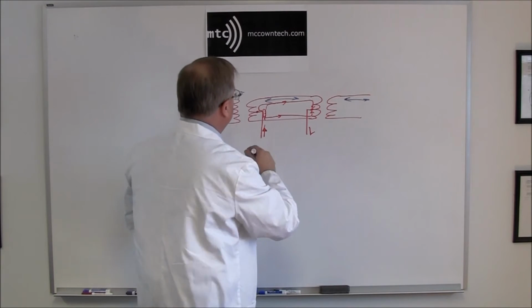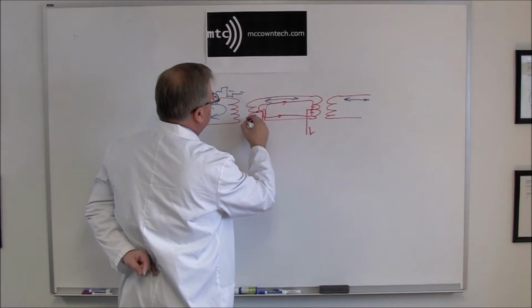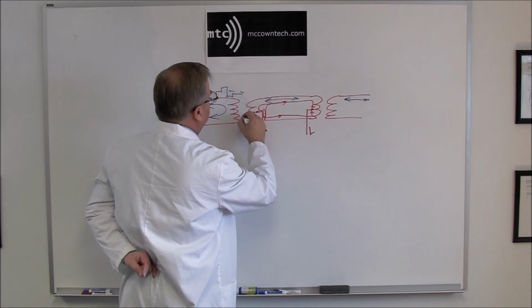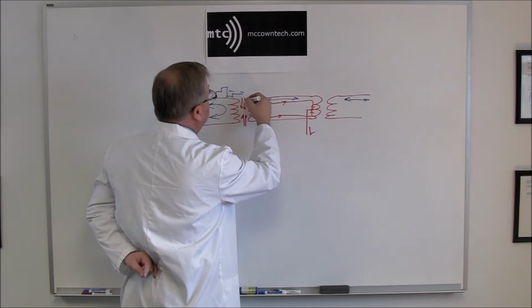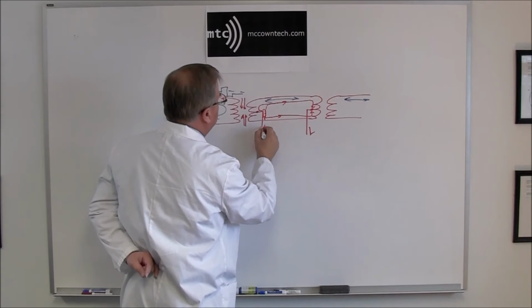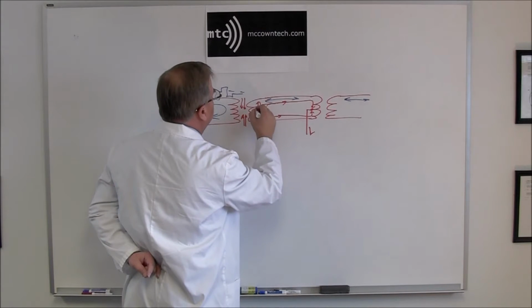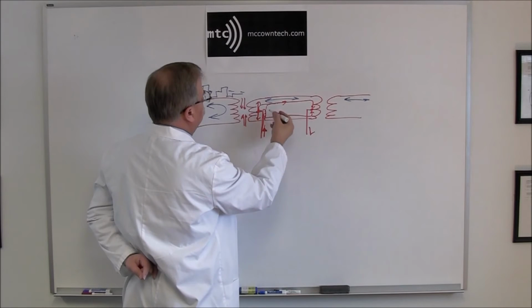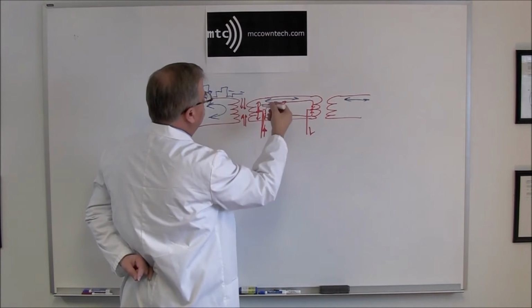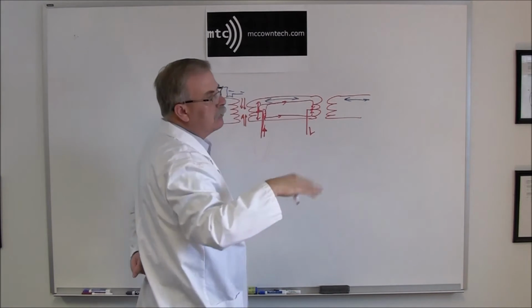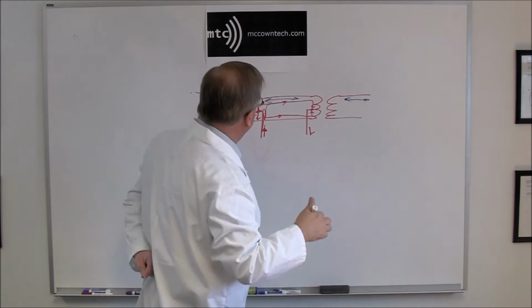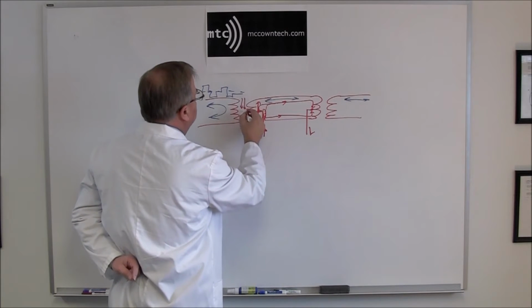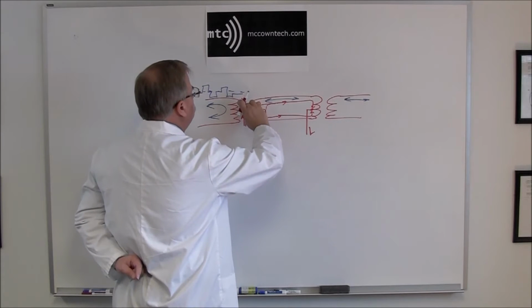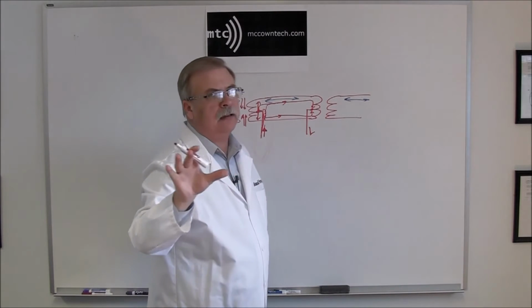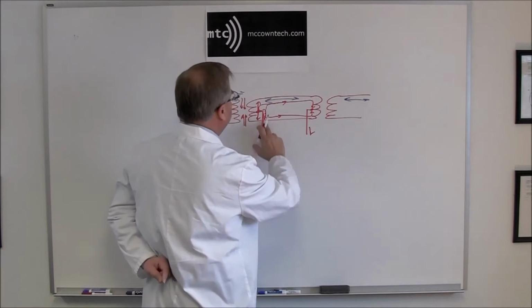The interesting thing is the magnetic fields made by the current in this half of the winding are offset by the magnetic fields in this half of the winding, because the current goes up here and splits — it goes that way and that way. The direction of the current through the windings determines the north-south, and there's the right-hand rule and all of these rules, but all you have to know is: if you've got two norths together, or two souths together, they cancel out. There's no magnetic field there caused by this new current.